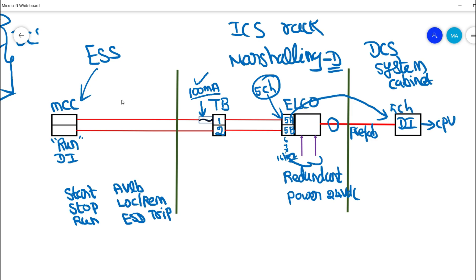From the digital input card, the signal goes into the CPU for indication and other control algorithms. This is the complete motor control signal loop running from the electrical substation to the motor control center, then into the digital marshalling panel, and finally into the DCS system cabinet. This is the loop diagram of electrical control signals.